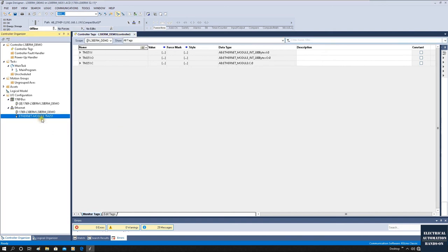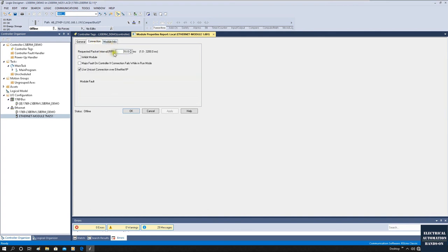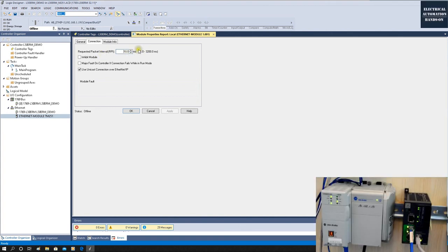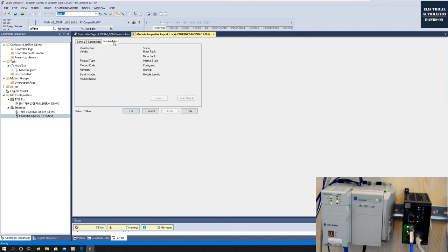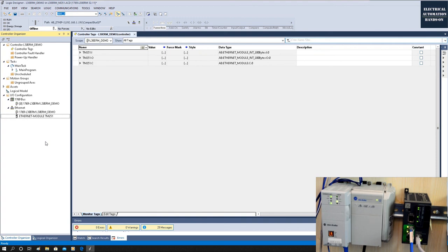To recap: we've manually set up the generic module using assembly 100 for input, 150 for output, configuration instance 1, with Integer (Word) format. Under the Connection tab, the RPI (cyclic communication time) can be left at 10ms default or set to 20ms depending on your application. We are still offline at this point.